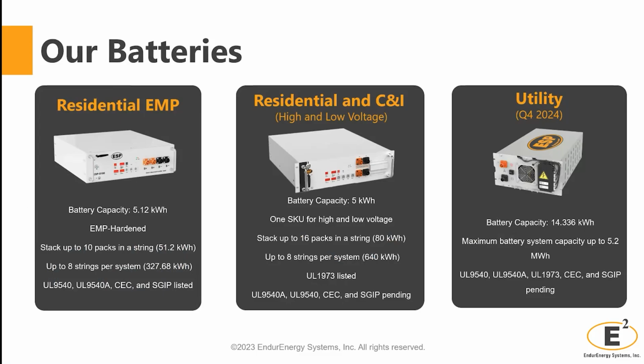This is going to be a look at our batteries. The one we'll be talking most about today is on the left, the residential EMP battery, similar to what's known as the 5100 but with EMP protection. That's a capacity of 5.12 kilowatt hours per battery. You can stack up to 10 packs in a string; after that you'll need the BCU, which is another product, very common for us to do. You can have 8 strings per system, and as you can see at the bottom, that is UL 9540, 9540A, CEC, and SGIP listed.